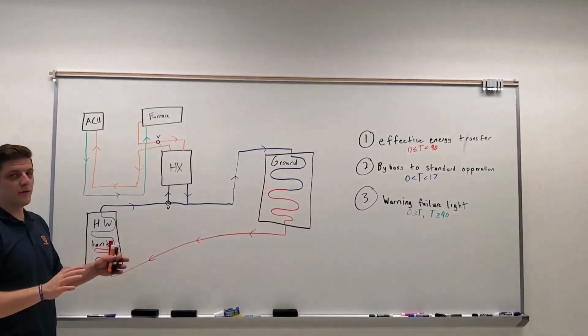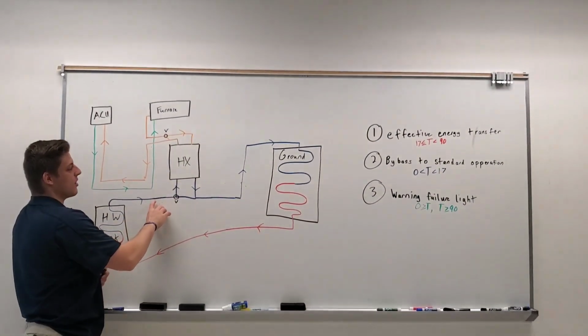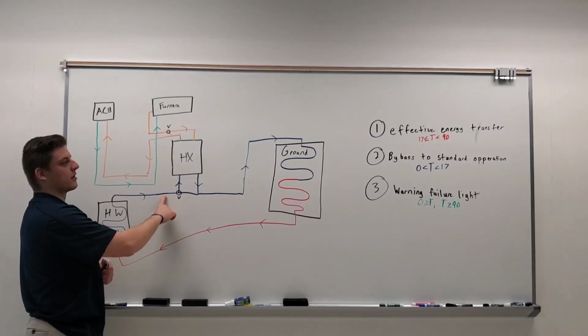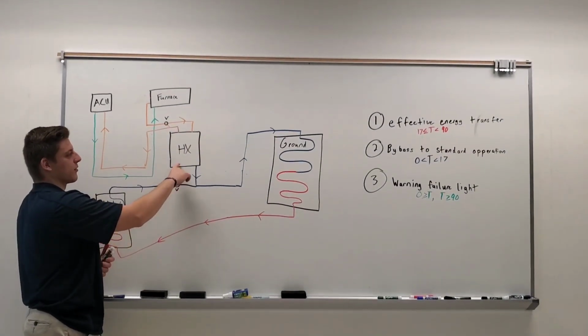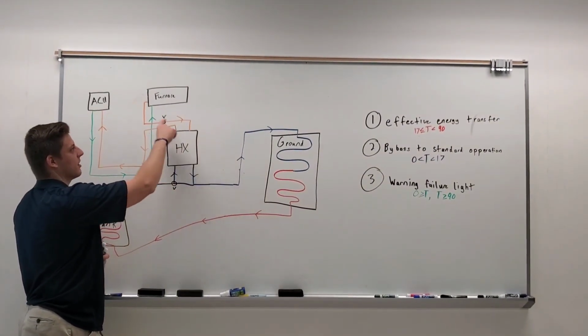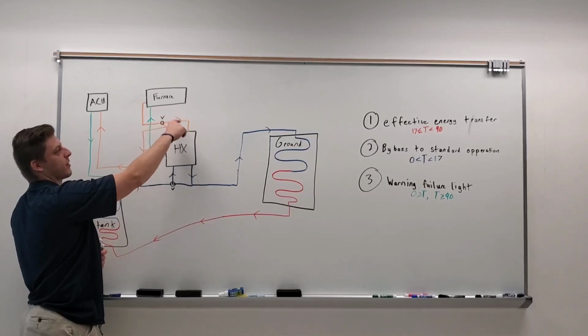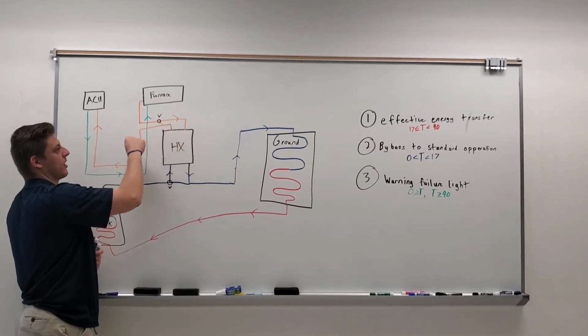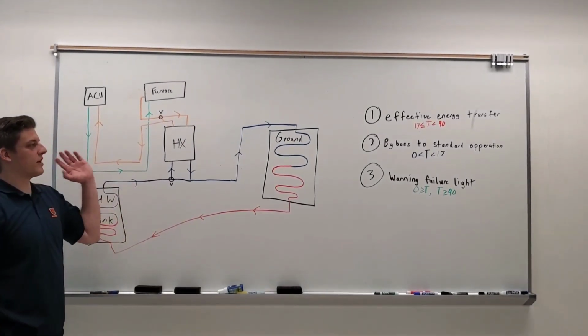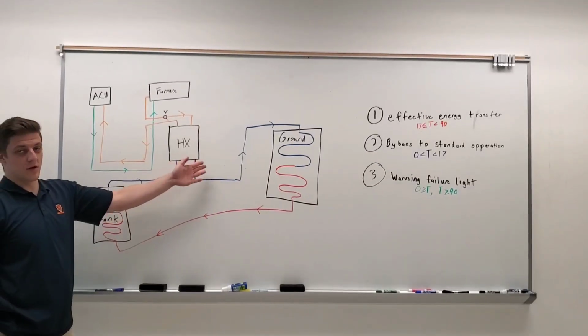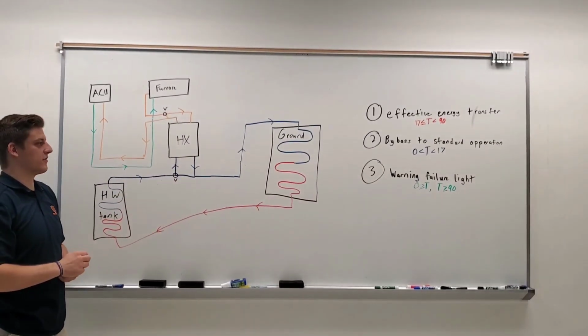Okay. So what we've done here is we've added this heat exchanger. We've taken our domestic water loop and put it through this heat exchanger and then continued on. And we've taken our warm refrigerant from our furnace and run it through there as well. So what this does is it allows us to preheat our water going through this loop, which increases energy effectiveness.